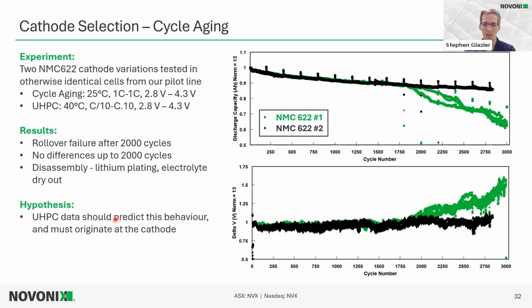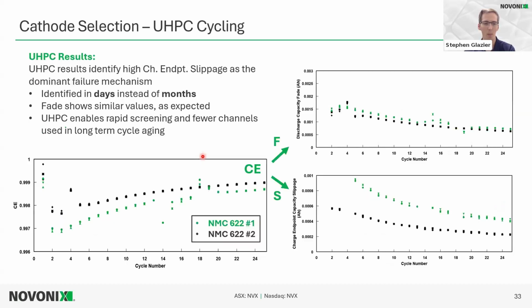So we use UHPC on any, or all, of our materials development. After formation, we put some cells onto long-term cycling and other cells onto UHPC cycling. And in just days instead of months of cycling, we can look at metrics like coulombic efficiency. You can see here this really zoomed in axis with triplicate cells. So these are measurements we have very high confidence in. There's very good accuracy, resolution and precision required to make these measurements. And we can see just within days of this cycling that there's a difference in coulombic efficiency.